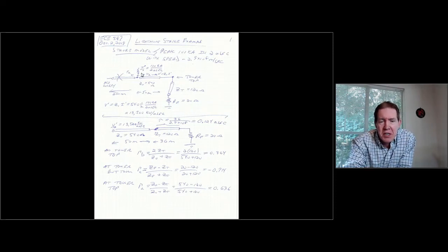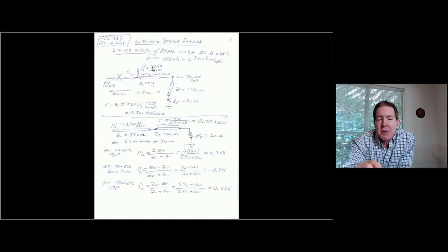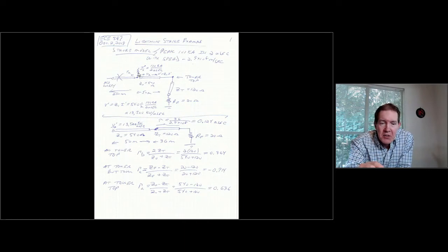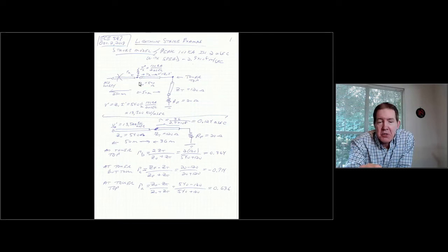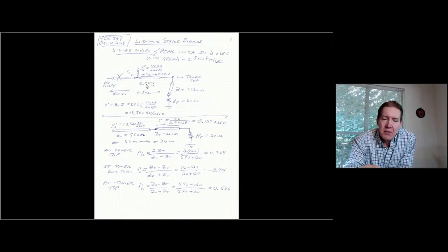When I do the modeling, I'm going to use a prime value notation, where prime represents a rate of change — a slope. So this slope is going to be 100 kiloamps divided by 2 microseconds. Because the lightning hits 50 meters out from the tower and the surge impedances in the left path and the right path are the same, the current is going to split — basically a current divider effect — so half of it goes to the right toward the tower.